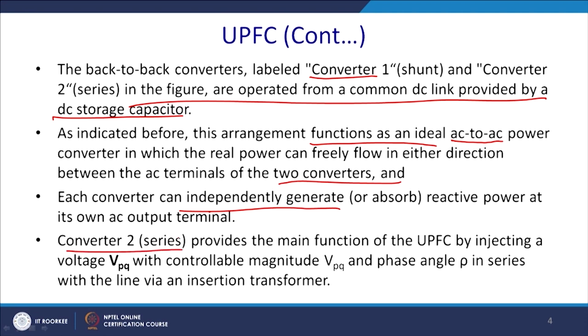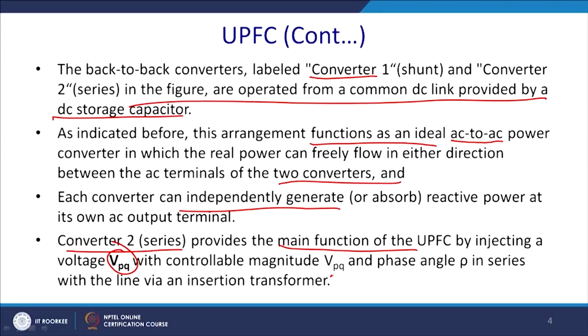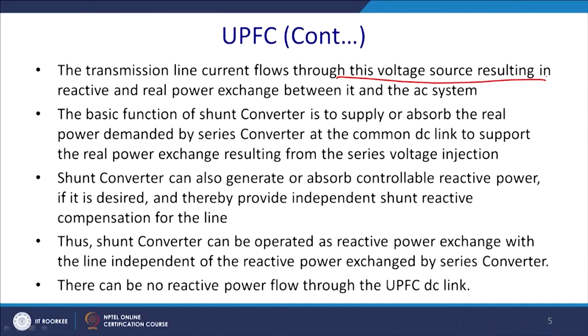Converter 2, that is basically the series one, acts as an SSSC and provides the main function of the UPFC by injecting the voltage Vpq as desired by the different modes of operation, with controllable magnitude Vpq and phase angle rho in series with the line via the insertion transformer. The transmission line current flows through this voltage source, resulting in reactive and real power exchange between the UPFC and its AC system.